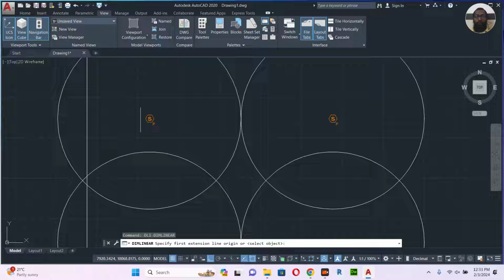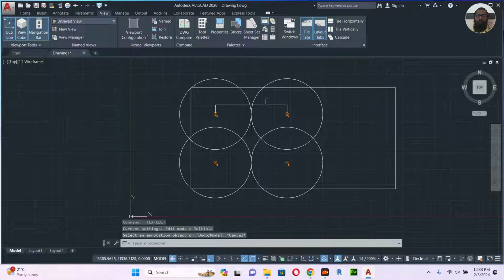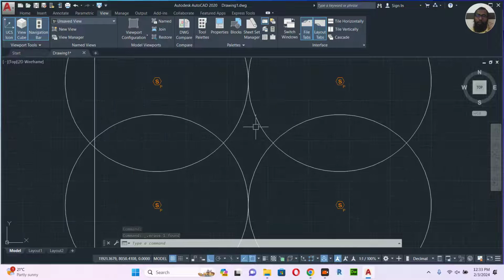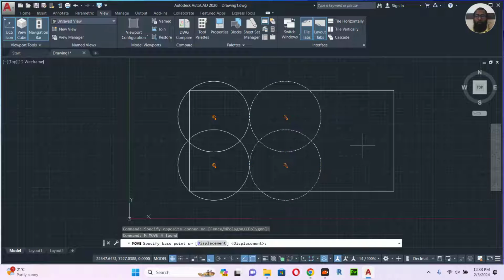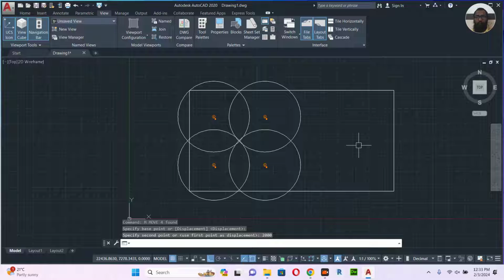So if you check this one here to here, it says almost 7 meter. So you see when I am taking 7 meter, this can cover 7 meter diameter, but here you see there's a blank spot, sorry, blind spot. So let's take this one. We will go 2 meter inside. So it's almost covering every area.